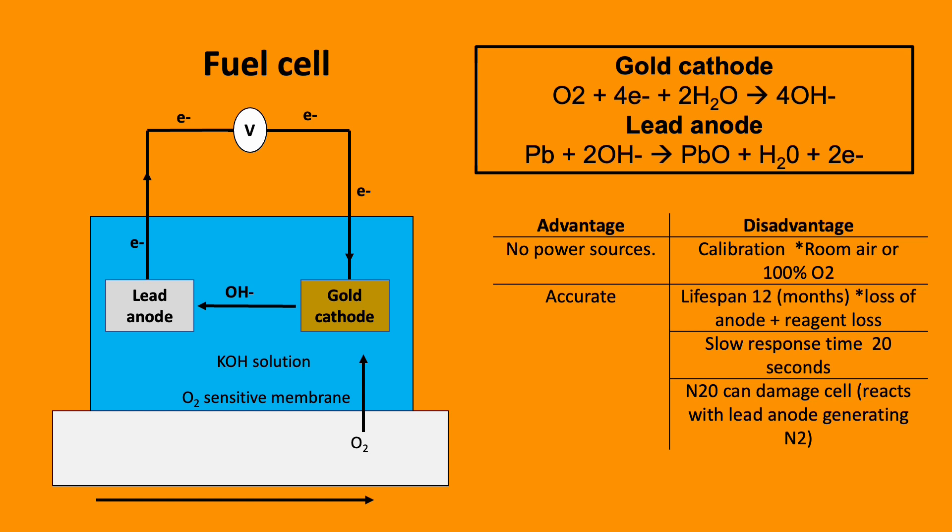How does it work? Oxygen diffuses across the O2-sensitive membrane and binds to the gold cathode. A reduction reaction occurs producing hydroxyl ions which move through the electrolyte solution and react with the lead anode. An oxidation reaction occurs at the anode, producing electrons which move around the circuit. Oxygen consumption is proportional to the current generated.